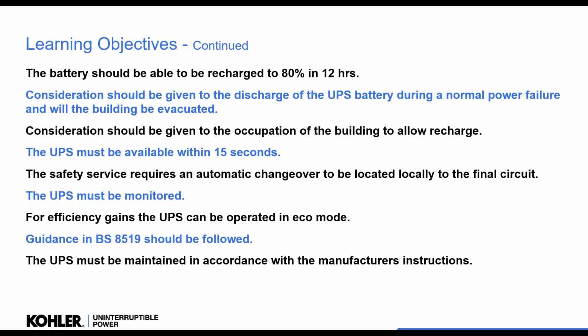The UPS must be available within 15 seconds. No problem for a UPS. They can be online instantly. Okay. We'll have an ATS locally to the final circuit where the secondary sources come in. Okay. Even if you've got a UPS feed in the final circuit, it might be a requirement that you have an ATS, unfortunately due to the regs. Okay, and then we must monitor it too, so we know the status of it. Okay, the UPS is there as a secondary source, so quite often they're not running the load normally. So there are ways we can get the efficiency up by putting the UPS in an offline eco mode. The UPS will come on and make itself available when required.